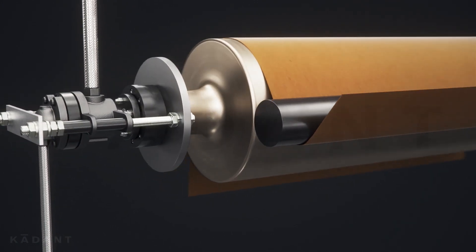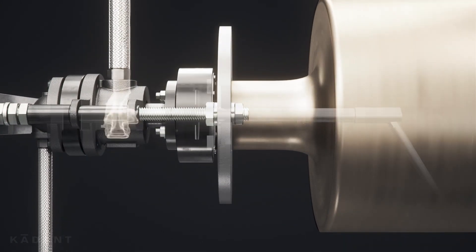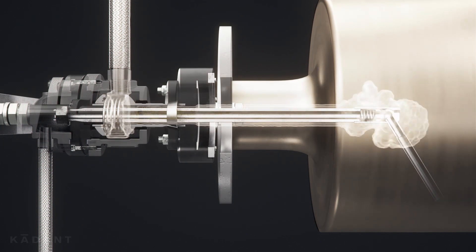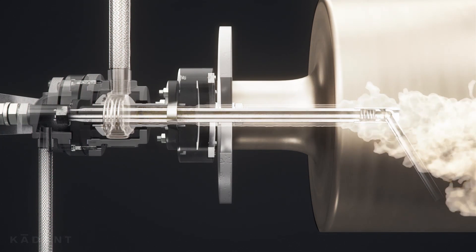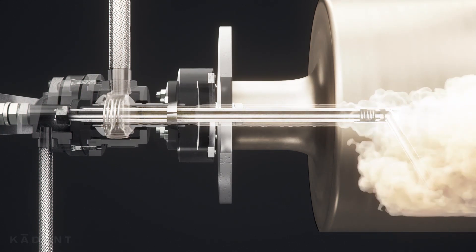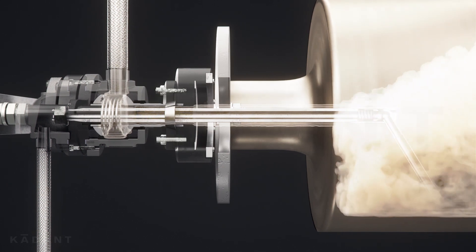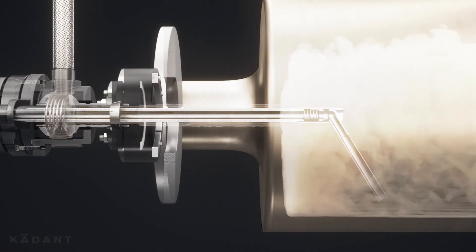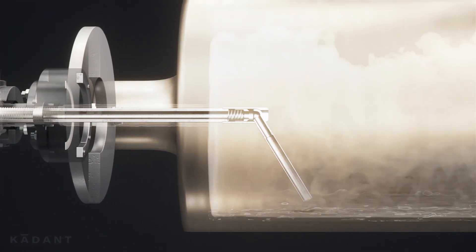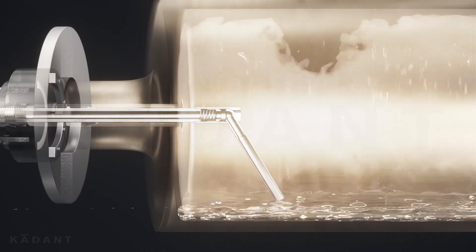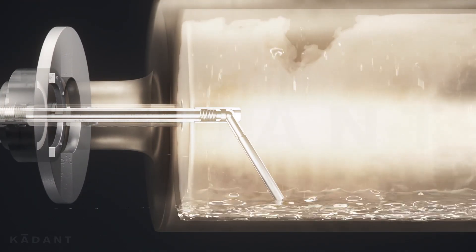The LJX rotary joint and rigid siphon system manages the steam distribution and condensate recovery inside the roll. Steam enters the rotary joint and travels into the roll. As the steam condenses on the surface of the roll, it releases its latent heat and puddles in the bottom of the roll.